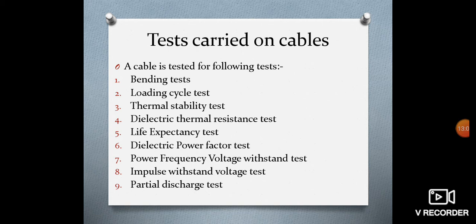Bending tests. Voltage test should be made before and after a bending test. The cable is bent round a cylinder of specified diameter to make one complete turn. It is then unwound and rewound in the opposite direction. The cycle is to be repeated 3 times. If it is able to withstand the bending test, then the cable is said to have passed the test.